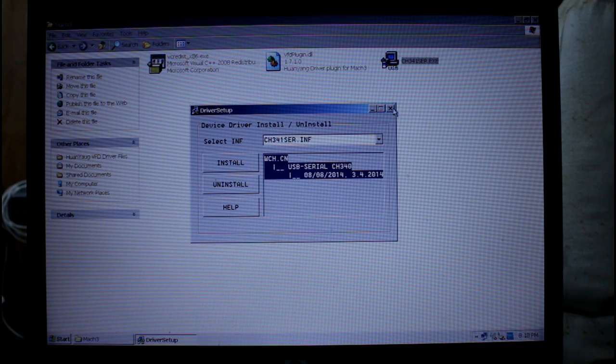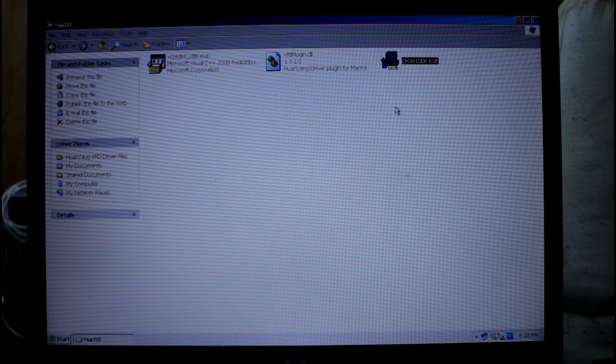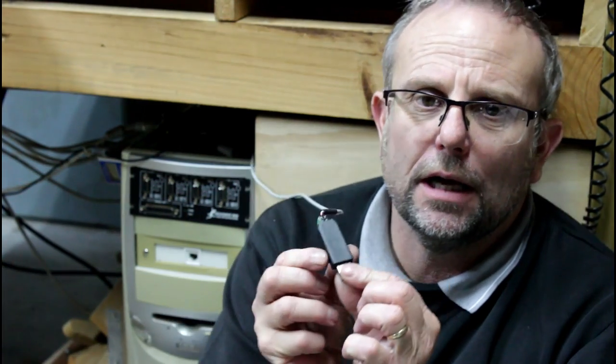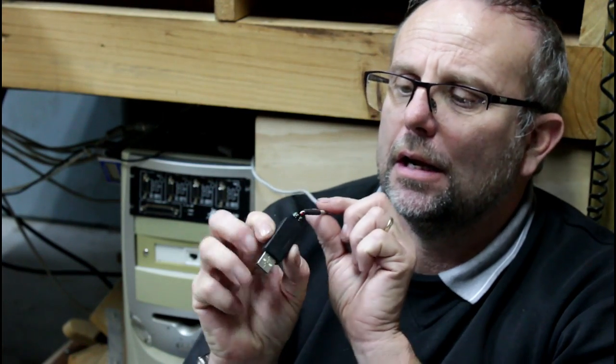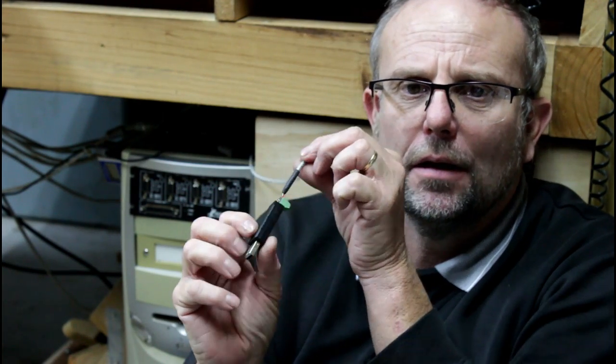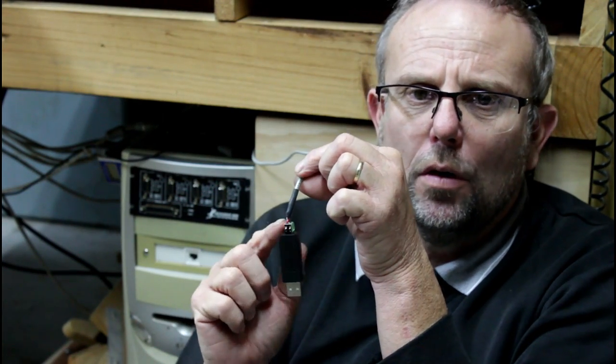So here's my RS485 adapter and I've connected it by two wires back to my VFD. They connect to the plus RS and minus RS contacts in the VFD and it doesn't matter if you get them around the wrong way, it won't hurt anything, it just won't work. So if it doesn't work one way you can always try reversing the polarity. Now one thing is important to note.